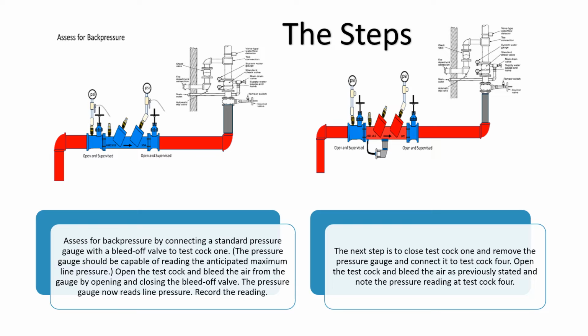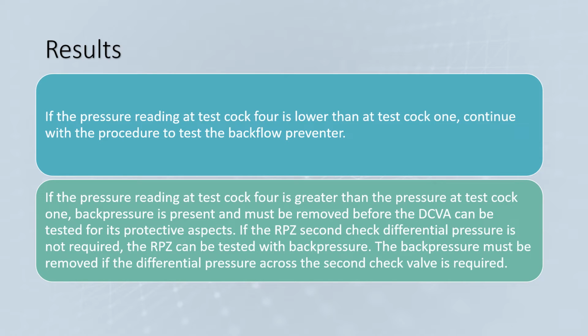Next, assess for back pressure by connecting a standard pressure gauge with a bleed-off valve to test cock 1. The pressure gauge should be capable of reading the anticipated maximum line pressure. Open the test cock, and bleed the air from the gauge by opening and closing the bleed-off valve. The pressure gauge now reads line pressure. Record the reading. The next step is to close test cock 1 and remove the pressure gauge, and connect it to test cock 4. Open the test cock, and bleed the air as previously stated, and note the pressure reading at test cock 4.